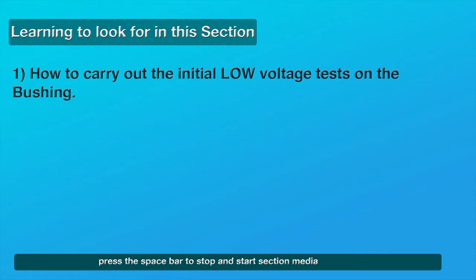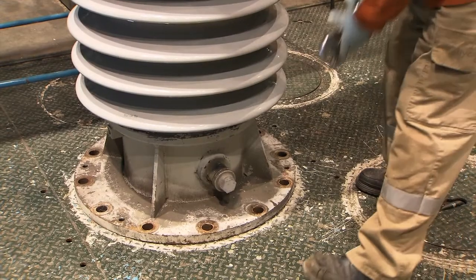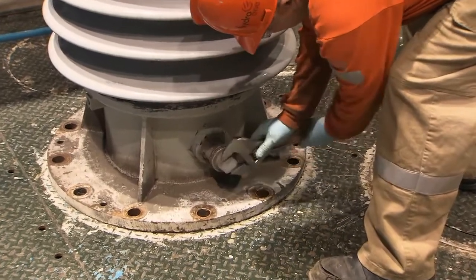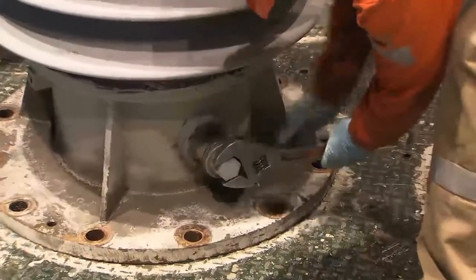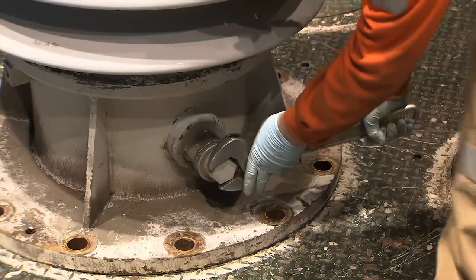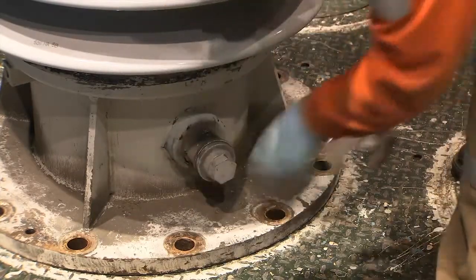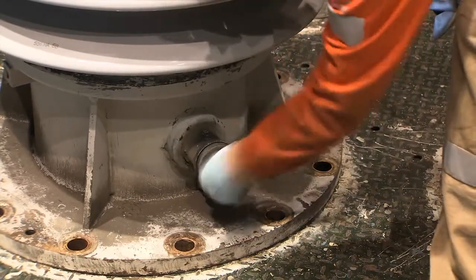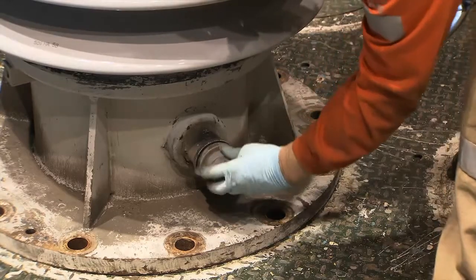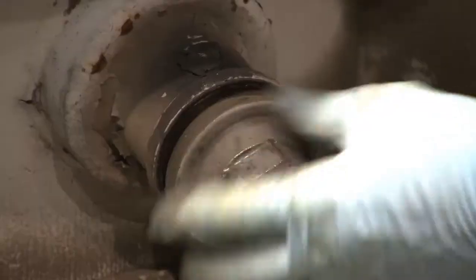Initial Megger and low voltage electrical tests for capacitance and the dissipation factor. After the bushing has been lowered into the service well, a series of electrical tests must be performed to determine if the main insulation wrapped around the core within the bushing is still intact. If significant degradation has occurred, it may not be worth refurbishing.